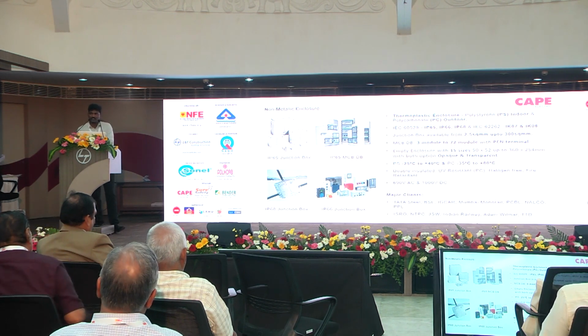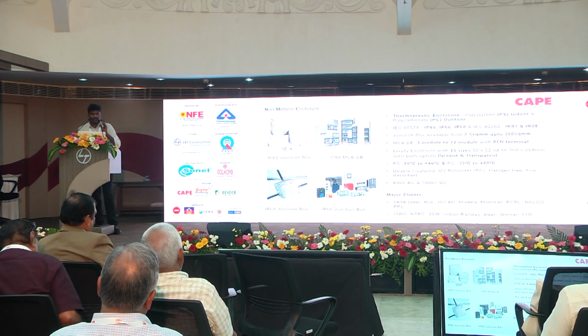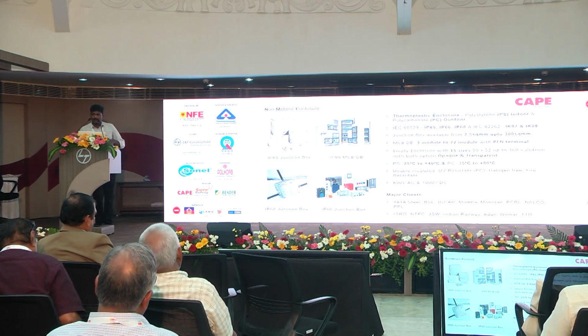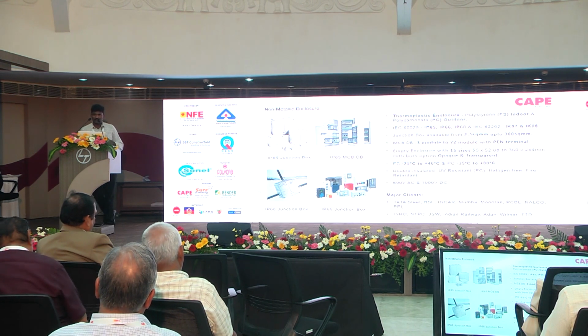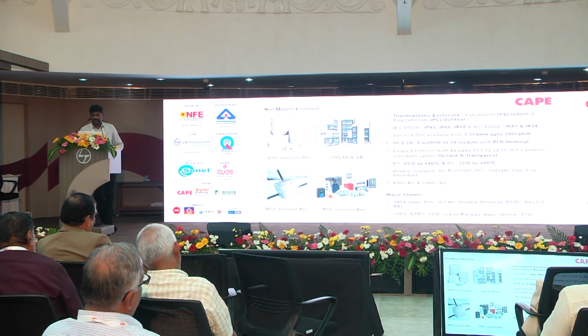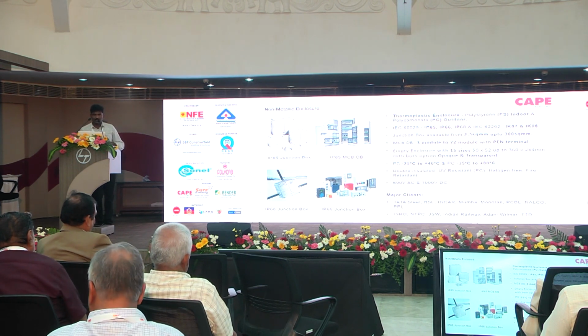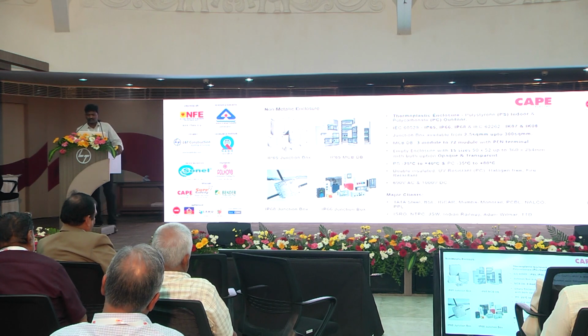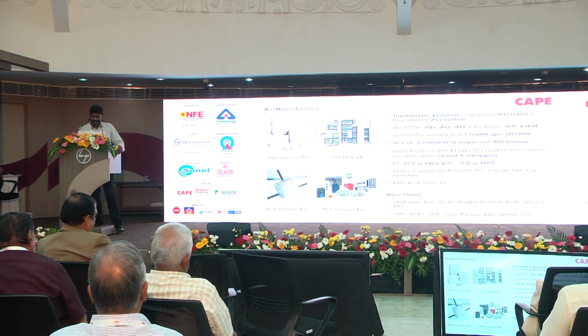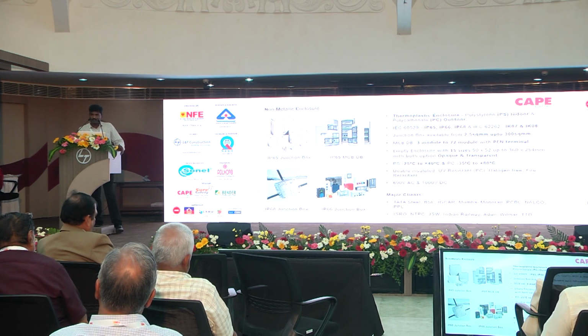Here we have two different ranges of products, PS and PC. PS can be used indoors only because it is not UV resistant. If you use this material outside, it will become brittle within 1 year. PC is a UV resistant material which we can use outdoors. We have junction boxes from 2.5 square mm to 300 square mm, and MCB DBs from 3 module single pole MCBs to 72 module single pole MCBs. We can combine these enclosures to make panels, which we show in the next slides. Major clients for this are Tata Steel, BSL, IG Care, Mumbai Monorail, Philips Carbon Black, National Aluminium Corporation of India, and National Thermal Power Corporation, which collaborated with Tamil Nadu Power Generation also. These materials are completely double insulated, so there is no requirement for body earthing.